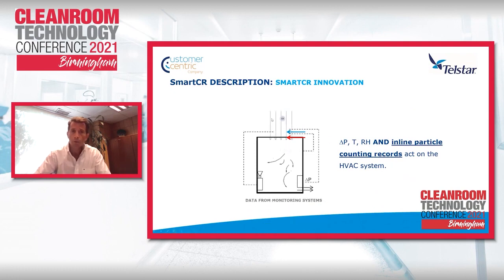You will have, as always, the supply air in the room. You will have one or several particle counters in the room, depending on the risk assessment we make. We will have the return air and the differential pressure with the surrounding rooms, and you have temperature and humidity. So these will be the 4 parameters acting on the HVAC system: differential pressure among the different rooms, temperature, relative humidity, and airborne particles in the room.